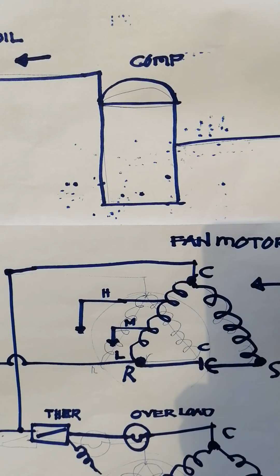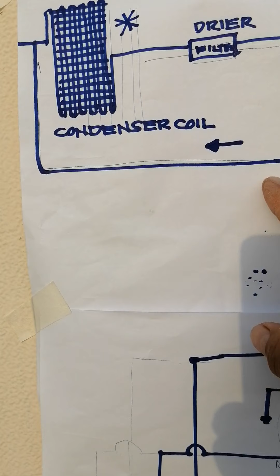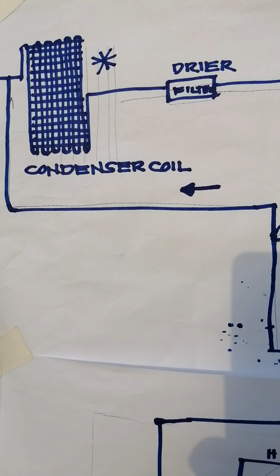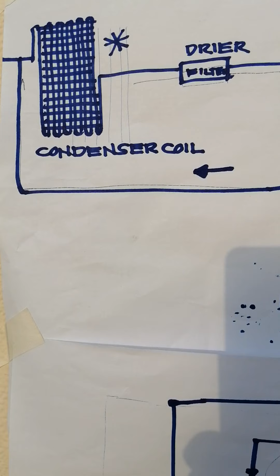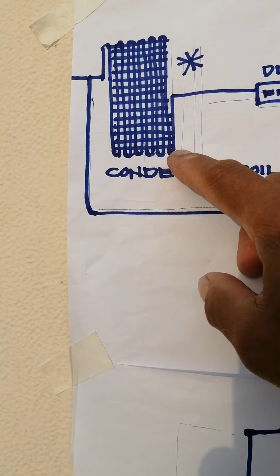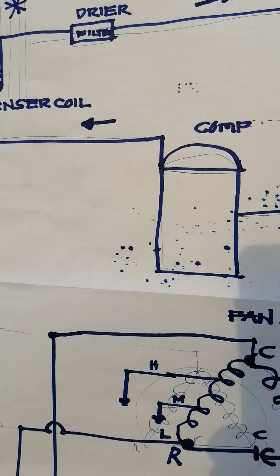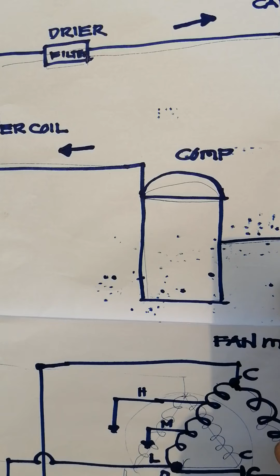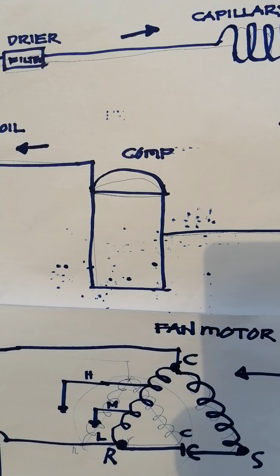Now, how about the compressor? This one is running, then afterwards stops, then again runs. What is the possible cause? So now we will go back to our block diagram. As you can see here, if this filter is choked or this capillary is choked, our compressor gets more hot and high pressure and stops. So the possible cause is this filter choke or capillary choke, or the condenser coil is already clogged up. That is some reason why the compressor will not run. Okay, guys, that is only some, but there are many more causes that the compressor will not run continuously.